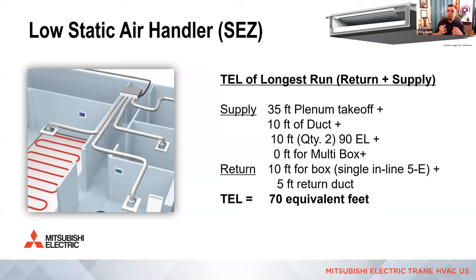So it's really important to use low value fittings here. Make it very easy for the air to make the turn, because we're not gonna have a lot of pressure to overcome bad fittings like bullhead tees or floor registers, right? If you're able to do this in a ceiling, it's a lot easier with those one piece register kits, okay? Of course, you do need a return duct. There's not a good picture here on the left. If we were in, let's say, an attic and we had a central return, we might have 10 feet for that box and then 5 feet of actual return duct going into the ceiling. So this is just a central return in a hallway.